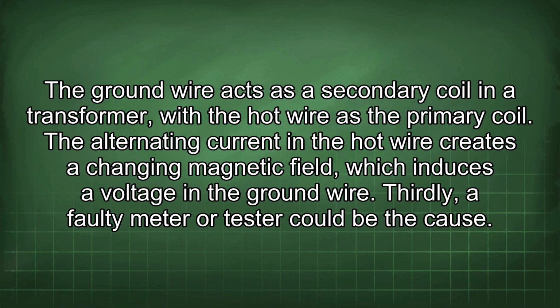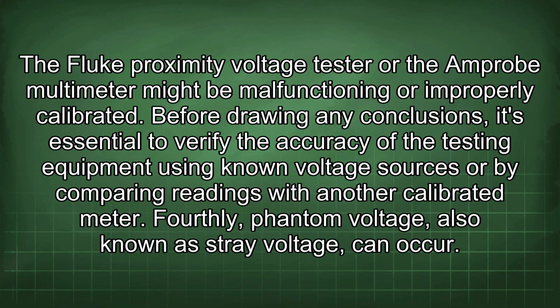Thirdly, a faulty meter or tester could be the cause. The Fluke proximity voltage tester or the Amprobe multimeter might be malfunctioning or improperly calibrated. Before drawing any conclusions, it's essential to verify the accuracy of the testing equipment using known voltage sources or by comparing readings with another calibrated meter.